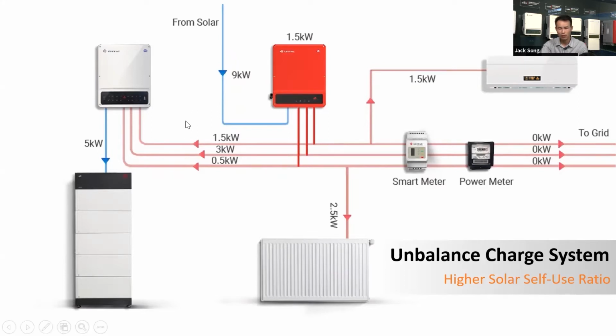So without the unbalanced output, unbalanced charge function, the power of 5 kilowatts cannot all charge the battery. They will charge the battery with 0.5 kilowatts on each phase, okay? But with the unbalanced charge function, each phase can have different power from the AC side, from the solar on-grid inverters, on-grid systems, to charge the battery, okay?